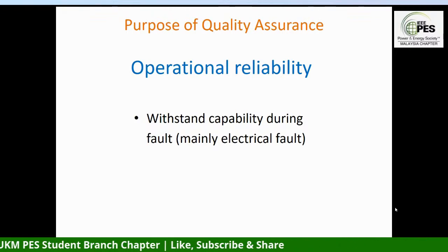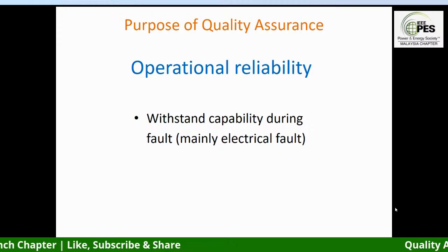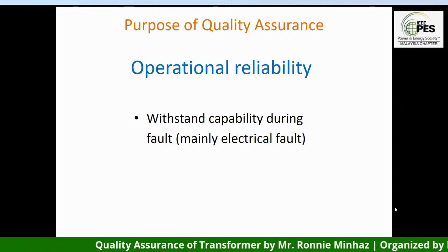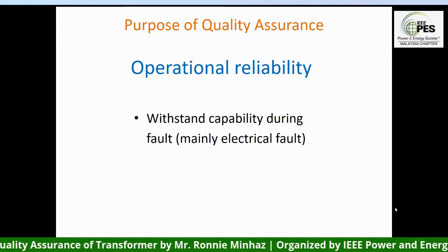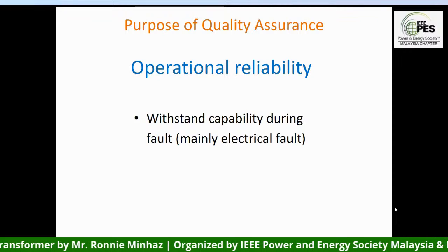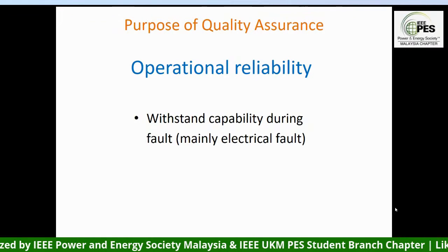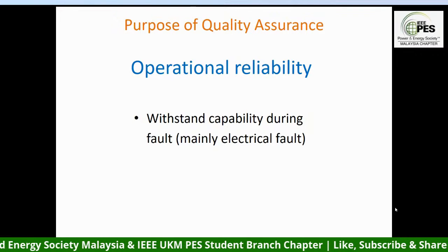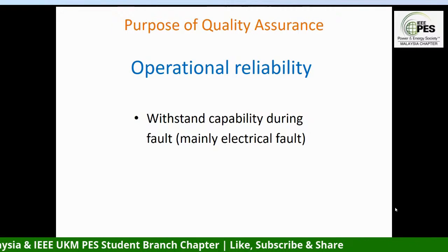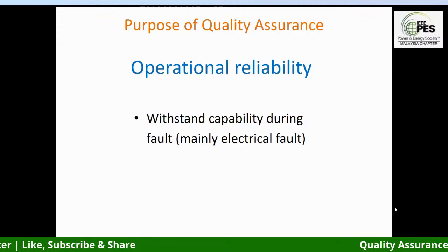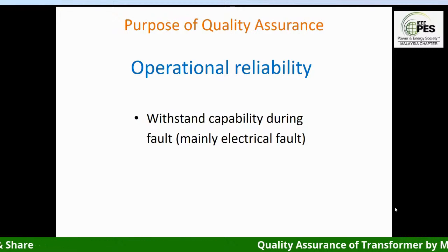So that's why they're not being stressed at the same level, especially the transformers from the mid 80s that we have procured, due to the quite extensive use of sophisticated computer programs. Now we are very aggressive in transformer design. Not only that, transformers are becoming more compact and more aggressive in design. So because we are not looking at some of the qualities that can be compromised during the manufacturing process, those are putting those transformers under higher stress due to the rise in the throughput.